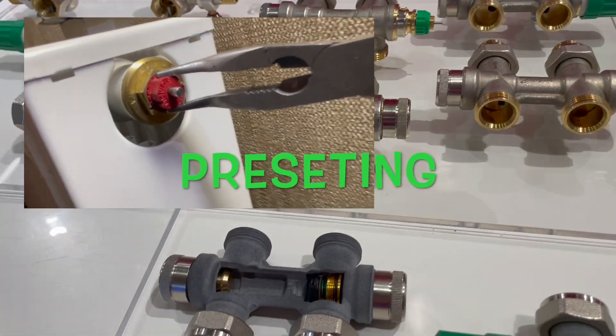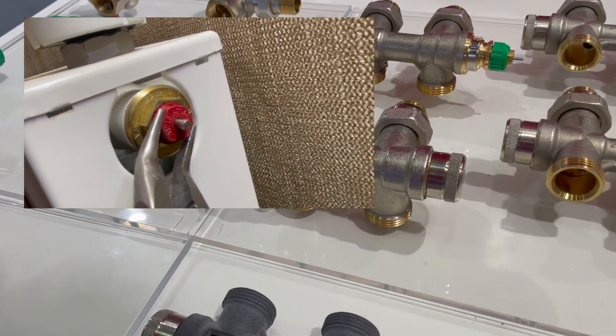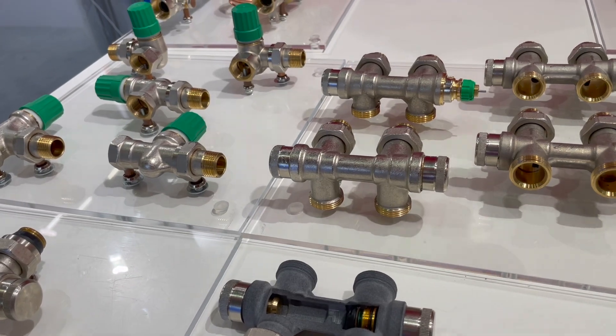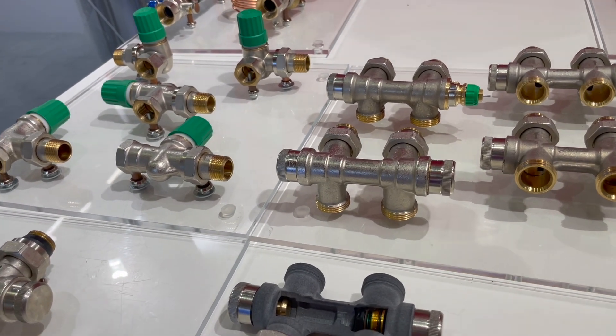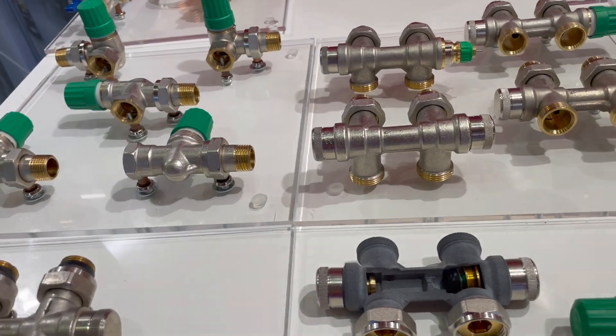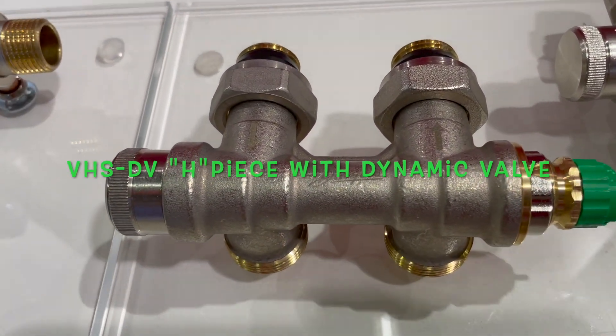So flow can be adjusted with the pre-setting of the radiator valve. In case the radiator valve does not have pre-setting, it can be changed into one that does. If you don't want to change the pre-setting or the insert of your radiator, you can use dynamic H-pieces with an already integrated dynamic valve.